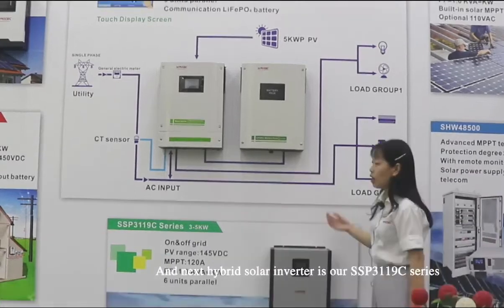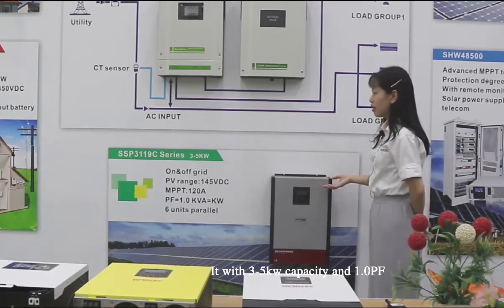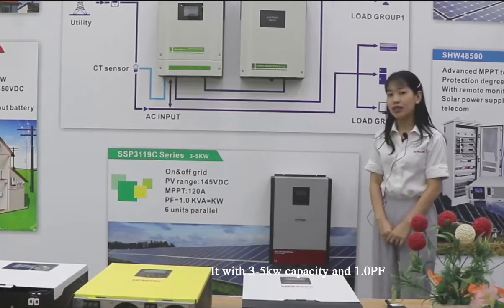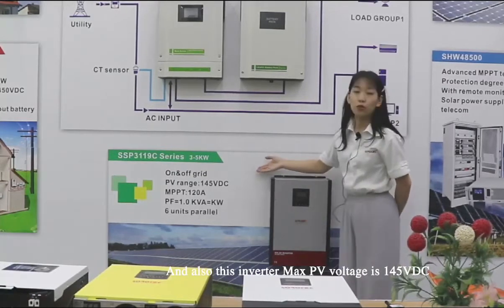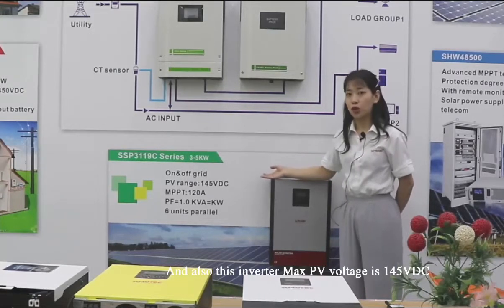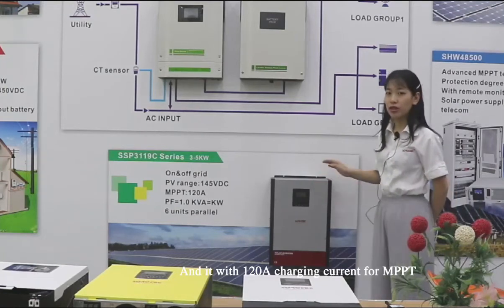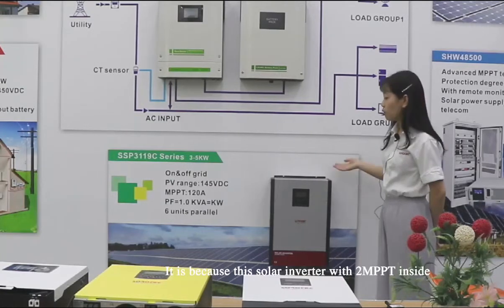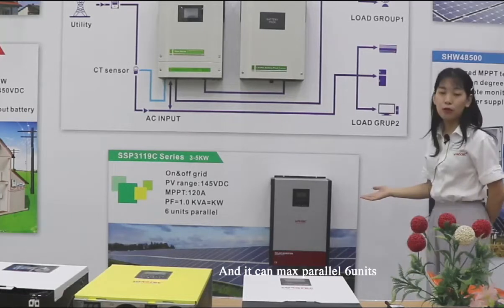Next, this hybrid solar inverter has 3 to 5 kW capacity and 1.0 power factor. The maximum PV voltage range is 145V DC. It has 120 ampere charging current for MPPT, because this inverter has 2 MPPT inputs inside. It can parallel 6 units.